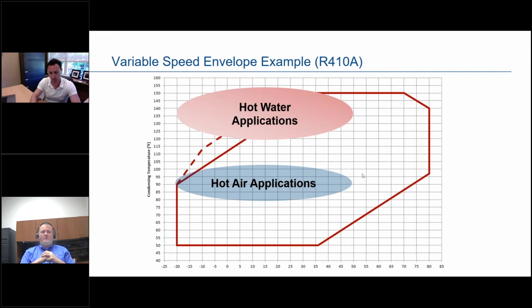Where you're going to struggle is more the hot water applications. As you can see, a good part of that application is outside the envelope, and you're also going to start losing capacity as you move up in the upper left side of the envelope, which is why the injection helps quite a bit there. There are vapor injection variable speed offerings. It's more of a new design approach that we're targeting now, and I think other OEMs and customer manufacturers are targeting it as well. It gives you the benefit of being able to overspeed, and also get extra capacity by injecting vapor or liquid into the scrolls to help cool the temperature as well.